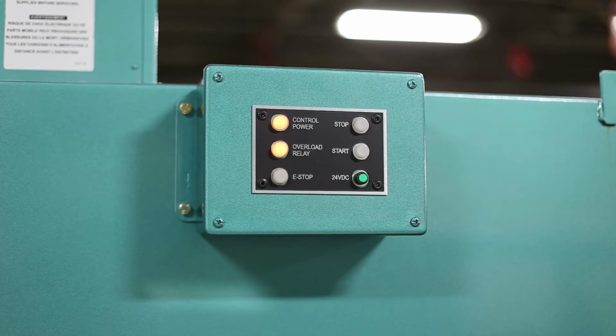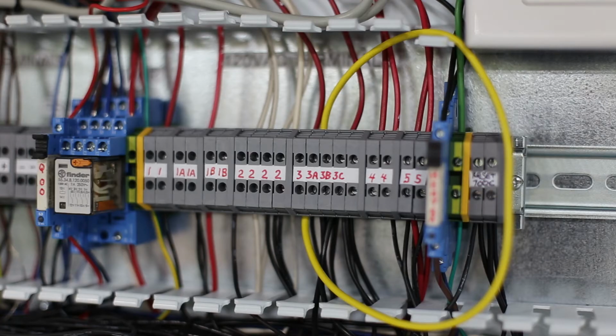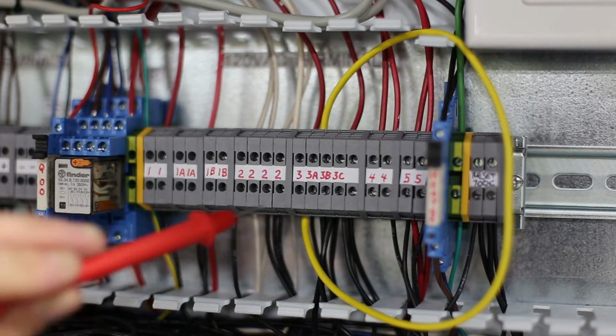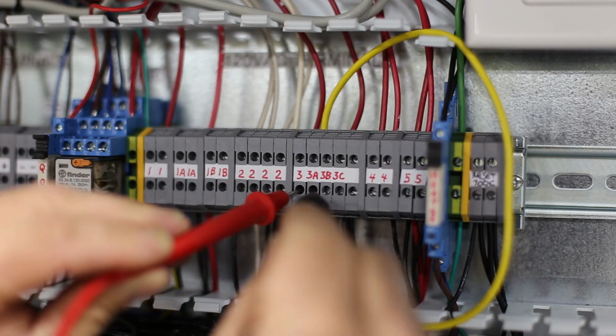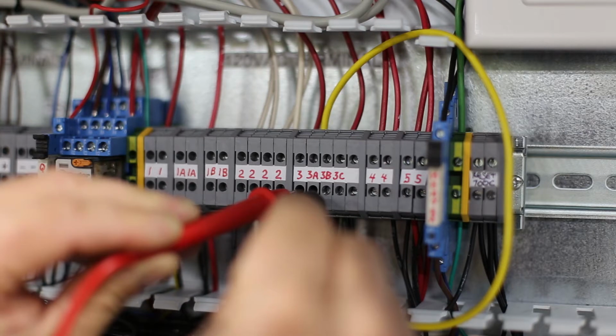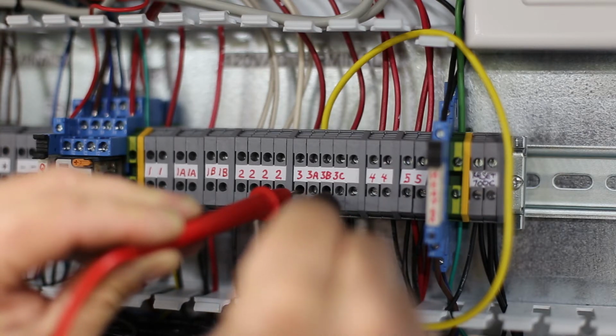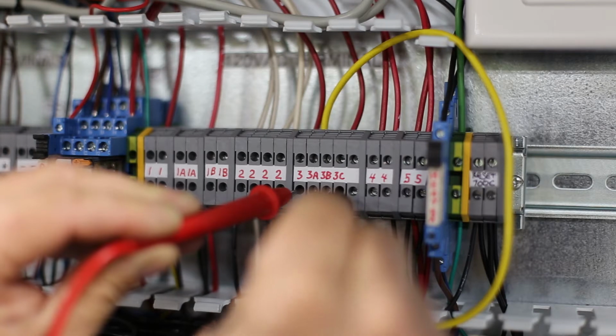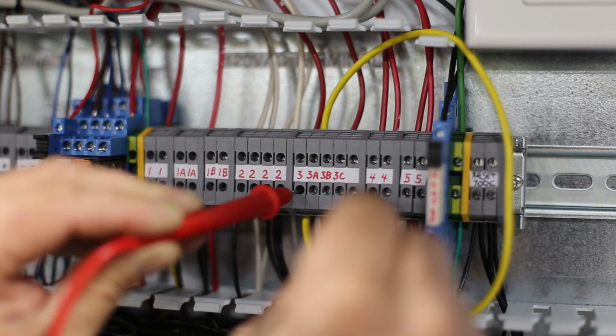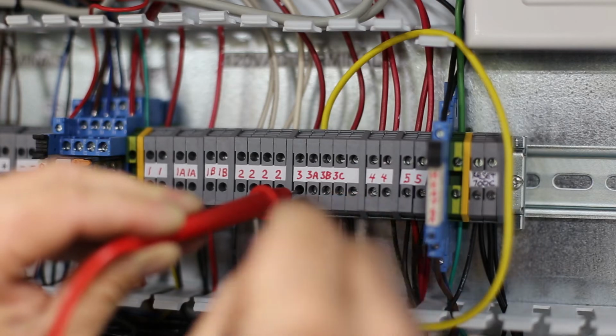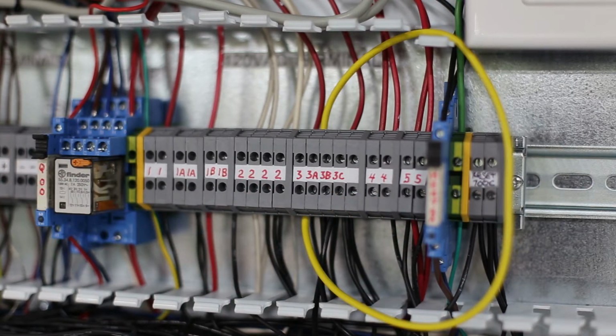So now that we have the control power, the overload on, the next step is our e-stop is not working. So again, we need to go look at our gate switch and our buttons to make sure our e-stop buttons or our gate switch is not open. The e-stop circuit goes from 3 through 3C to 4. So what we want to do is check for ohms between 3 and 3A. If you get 0, that means that circuit's been completed, so we move to 3B. And if that circuit's completed, we go to 3C. If that circuit's completed, we go to 4. And if all four, between 3 and 4, is met, that means our e-stop circuit is good.